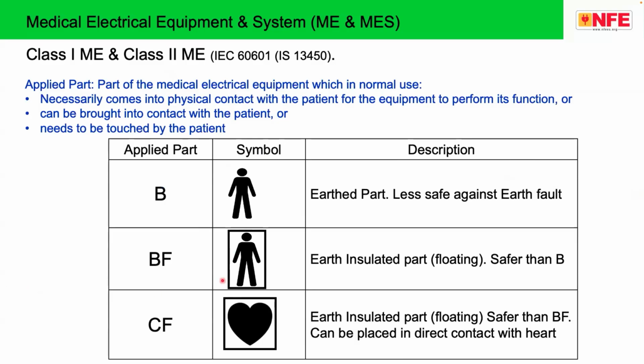Examples of type B applied part: the hospital bed, for example, because the patient is on the hospital bed. That is one example. Or the bore or table of patient MRI scanners, phototherapy units, the light fittings, ventilators, the main unit of the machine, all these are classified as type B.